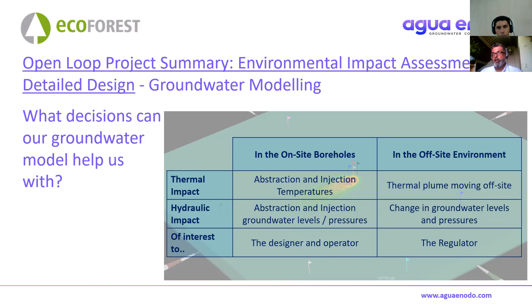This is an example of the thermal modeling we might do for an open loop system. The two flags next to each other are a cooling-dominant single pair ground source heat pump system, with an abstraction well on the left and an injection well on the right. Down gradient from that you can see another flag - that's someone else's abstraction well.